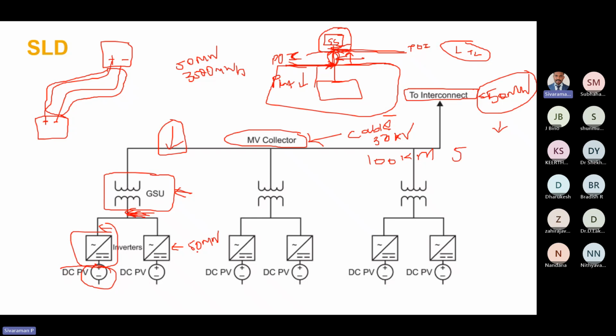So here the total inverter capacity is 50 megawatt, right? So the power at the interconnection point, P_i, equals 50 minus P losses in the AC cable at this location, cable losses in this location, then the inverter duty transformer loss, P_IDT, then the P collector network loss. We have to consider the collector network loss.